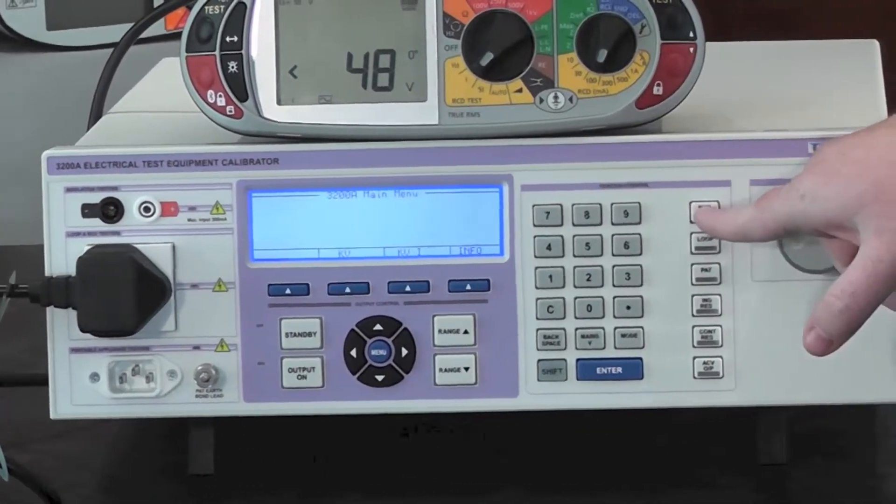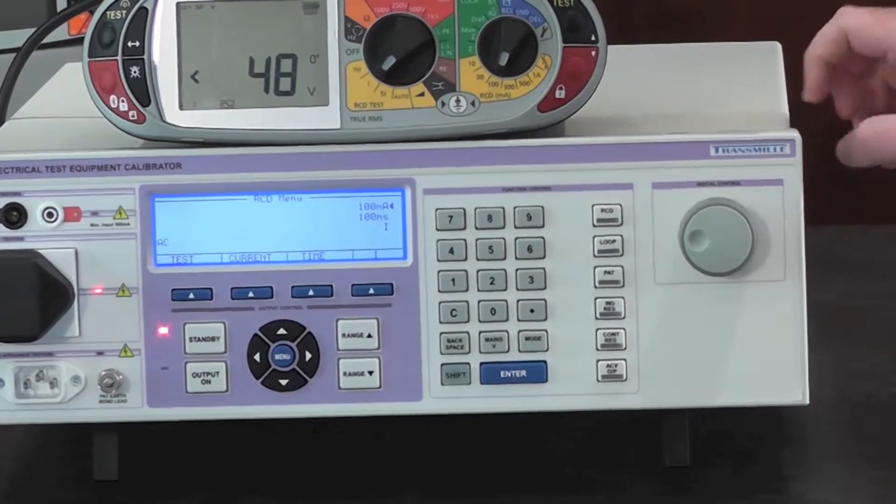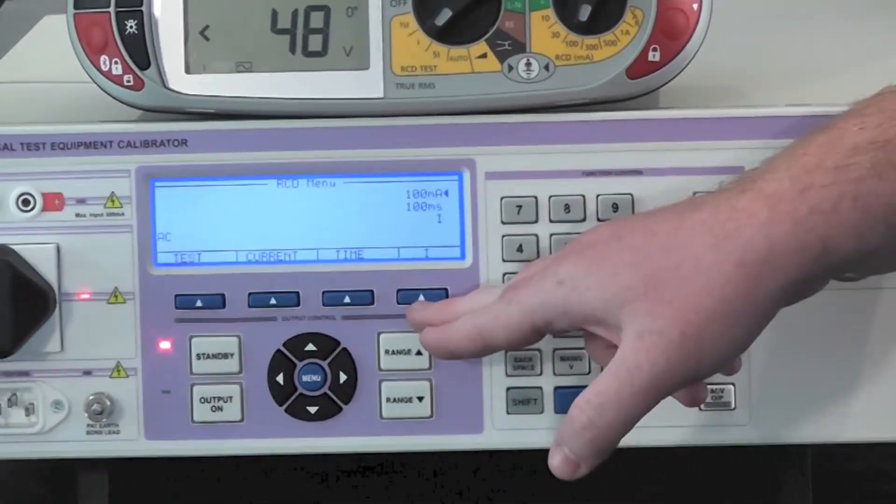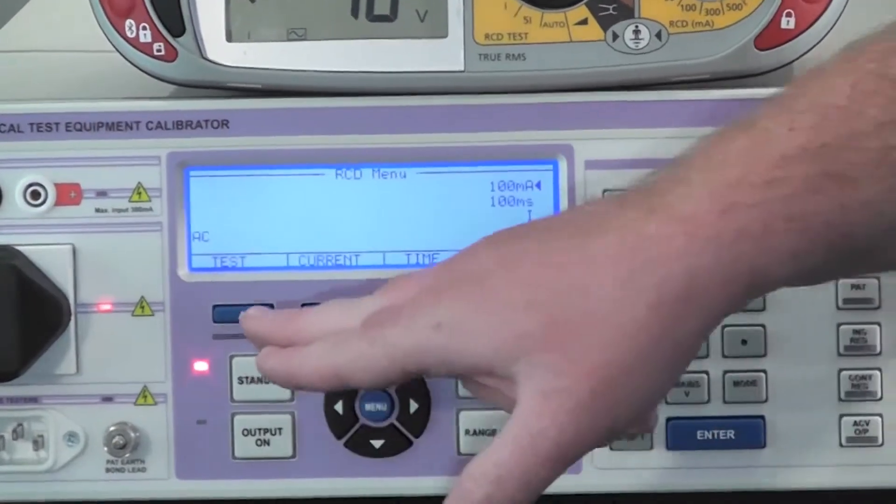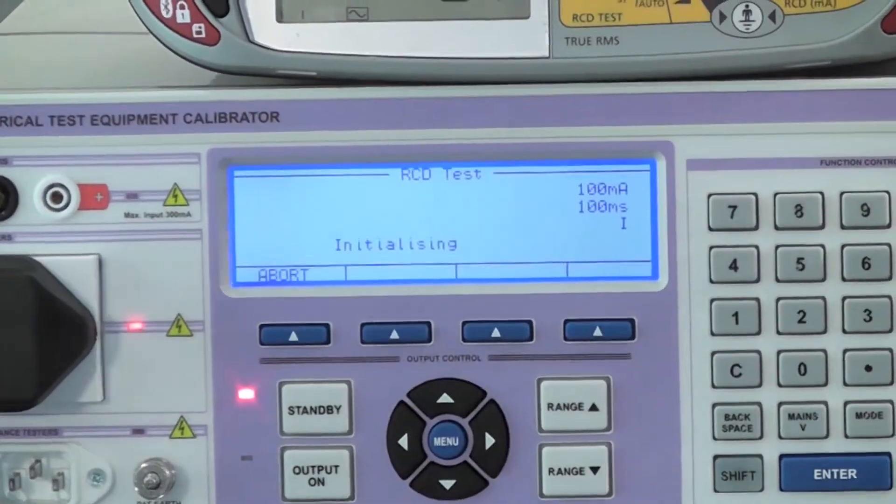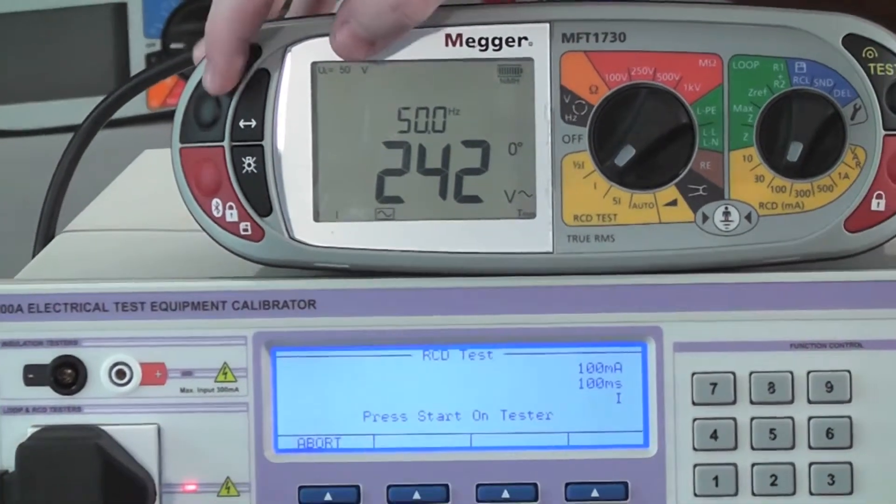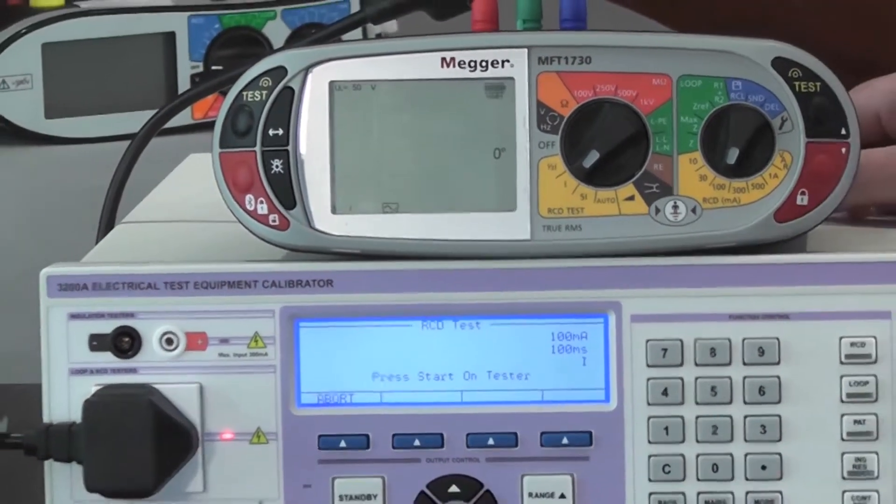Using the dedicated RCD key you can then select the current, the time and the current mode required. Simply press test, wait for the RCD tester to be ready and press test on the RCD tester.